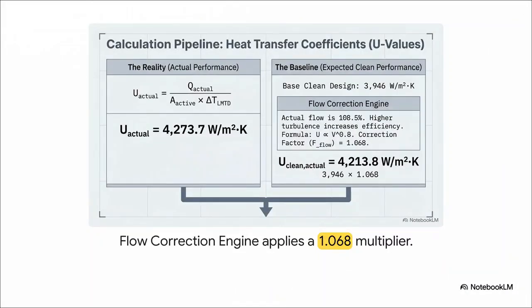The U values, or heat transfer coefficients. On the left, we calculate our actual performance based on the heat duty and LMTD we just found. That gives us an actual U value of 4,273.7. But look over at the right side, the baseline. The original clean design U value was only 3,946. So why the big difference? Well, remember that 8.5% extra cooling water flow we noticed earlier? We have to run that through a flow correction engine. Higher flow means higher turbulence, and turbulence naturally increases efficiency. So we apply a correction factor of 1.068 to the baseline. That raises our expected clean performance up to 4,213.8, which beautifully matches the reality of our current high flow state.